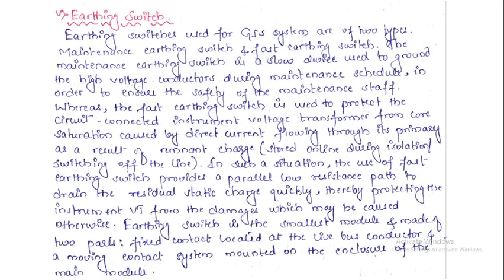of the maintenance staff. Whereas the fast earthing switch is used to protect the circuit-connected instrument voltage transformer from core saturation caused by direct current flowing through its primary as a result of remnant charge stored on the line during isolation or switching of the line. In such a situation, the fast earthing switch provides a parallel low resistance path to drain the residual static charge quickly, thereby protecting the instrument VT from damage which may otherwise be caused. So because of these remnant charges, instead of flowing directly into the instrument voltage transformer, they flow through the earthing switch rather than into the VT. Otherwise that VT may get damaged.